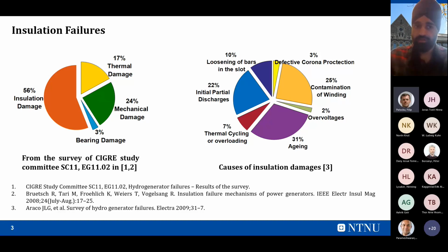Now this insulation damage can be divided further into different reasons why the insulation deteriorates with time. There are several reasons. One is the initial partial discharges, which play a major role at around 22%. Then there is contamination of the winding, and aging of the insulation, which takes the largest share, around 31% of the damage, because the insulation gets damaged with time. The second thing is loosening of bars in the slot. I'll explain in the next slide how this loosening of bars in the slot, the partial discharges, and the aging affect insulation failure.